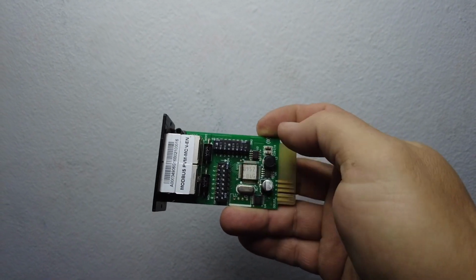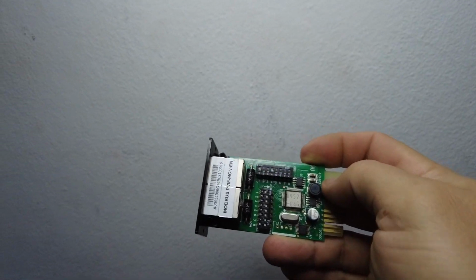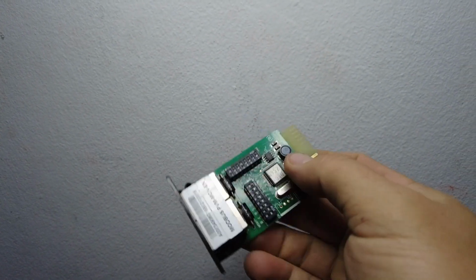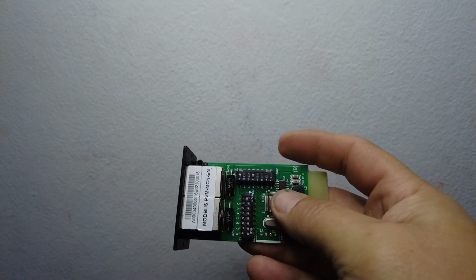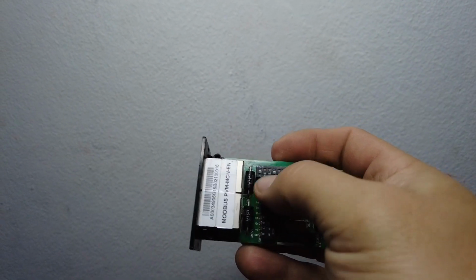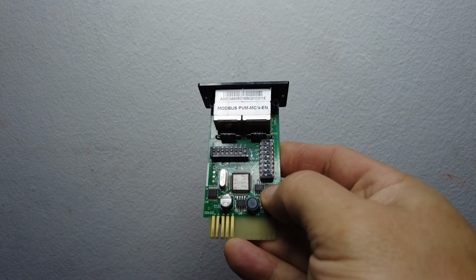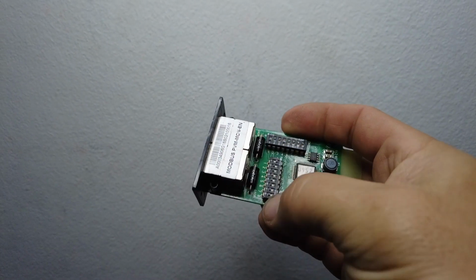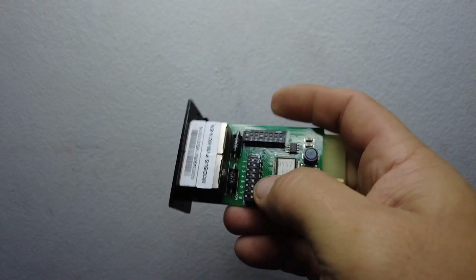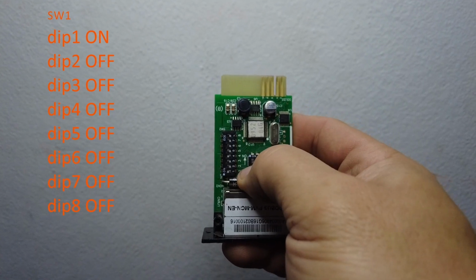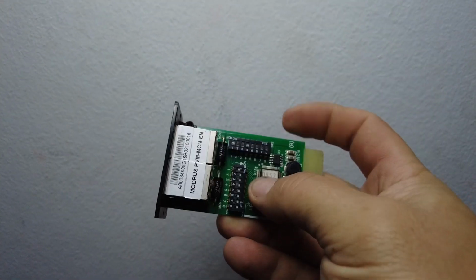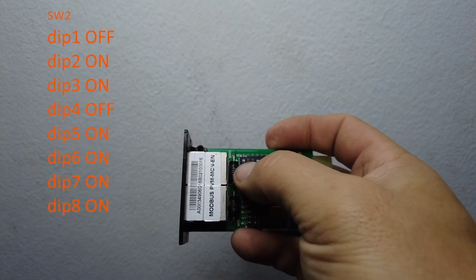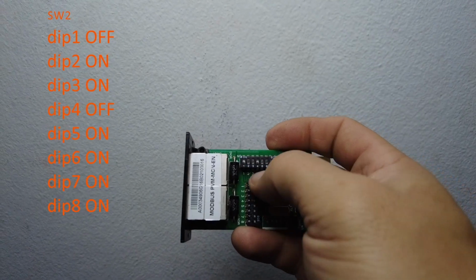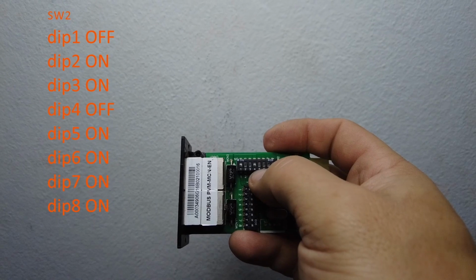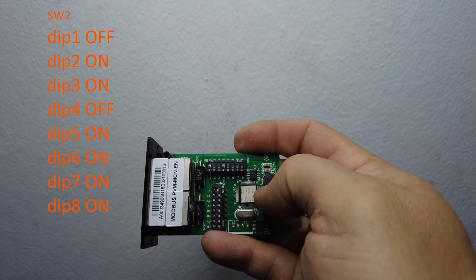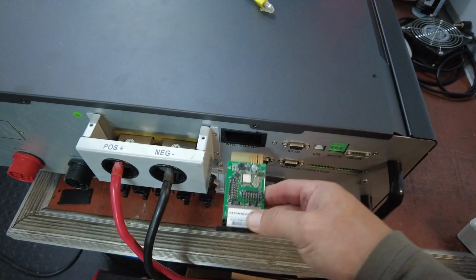So generally when you remove the Modbus card from the packaging, the dip switches you have on this card should be set correctly for the setup already. However, let's just cover it for argument's sake. This is your switch number 2. As you can see, it's labeled on the PC board, and this switch is switch number 1. So switch number 1, only your first dip is in the on position. And coming around to switch number 2, dip number 1 is in the off position, 2 and 3 are in the on position, dip number 4 off, and then 5, 6, 7 as well as 8 are in the on position.